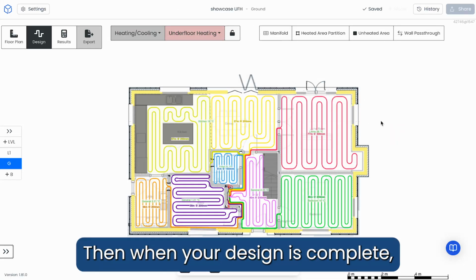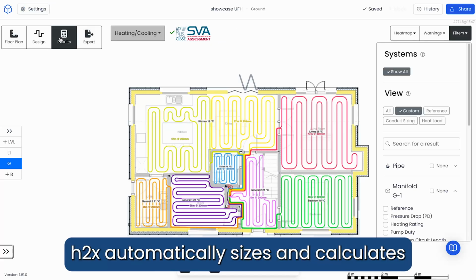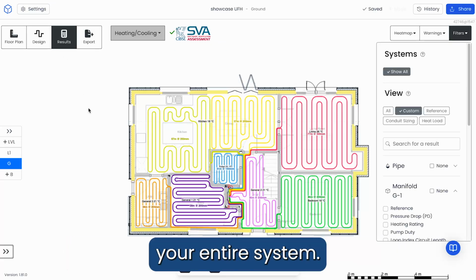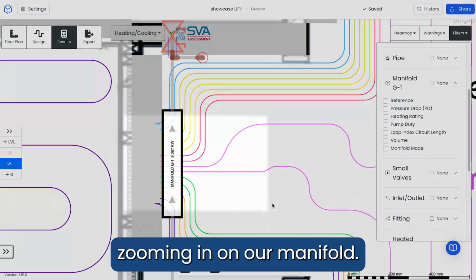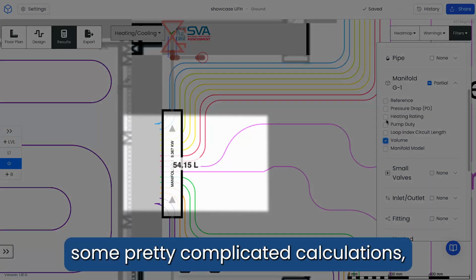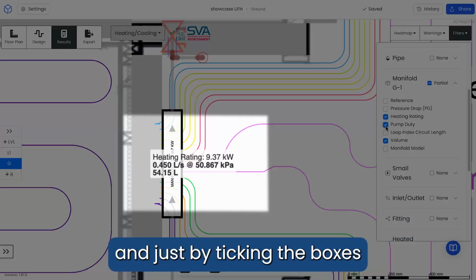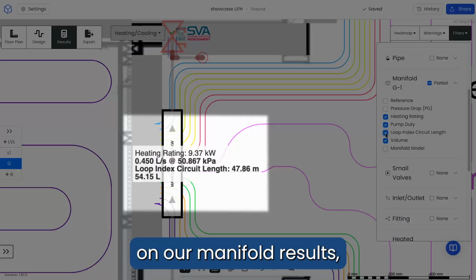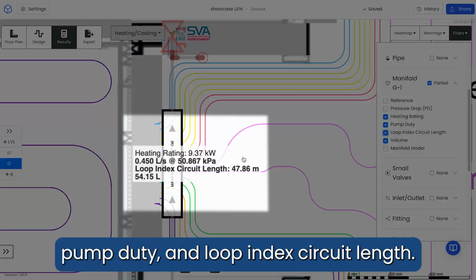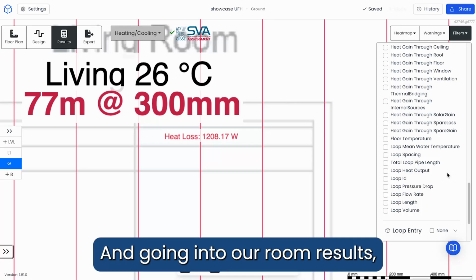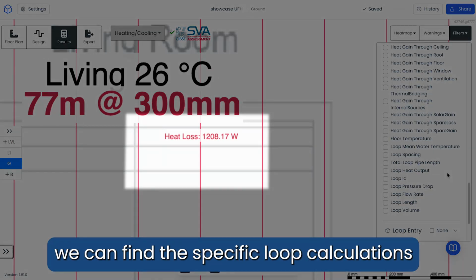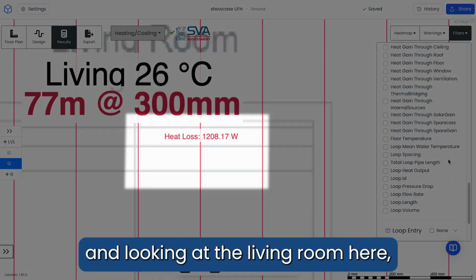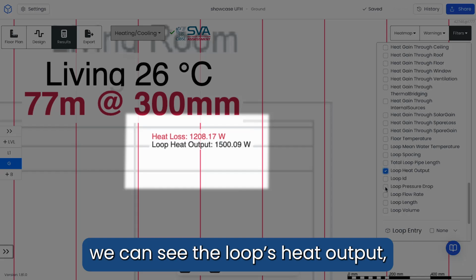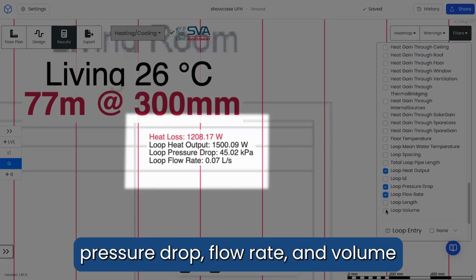Then when your design is complete, with just the click of a single button, H2X automatically sizes and calculates your entire system. Zooming in on our manifold, we can see that H2X has undertaken some pretty complicated calculations. And just by ticking the boxes on our manifold results, we can see the volume, heating rating, pump duty, and loop index circuit length. And going into our room results, we can find the specific loop calculations for each room. Looking at the living room here, we can see the loop's heat output, pressure drop, flow rate, and volume, among a myriad of other calculations.